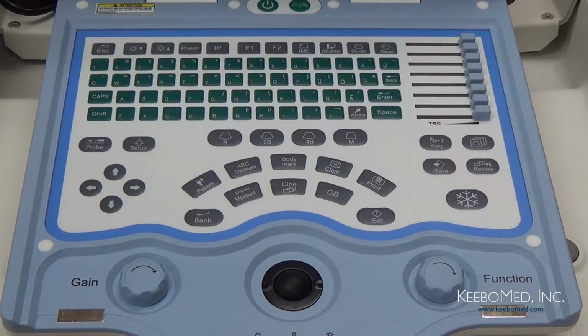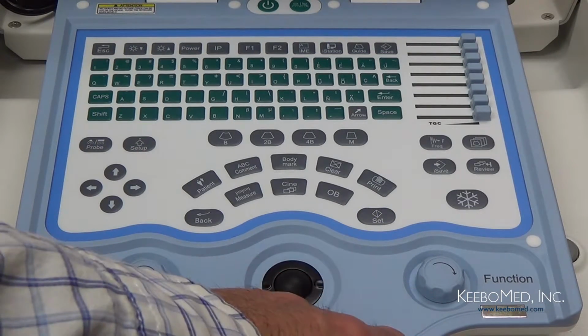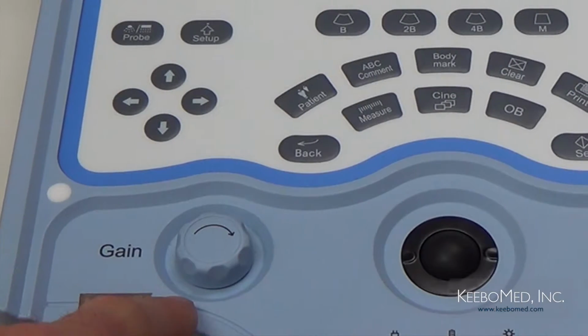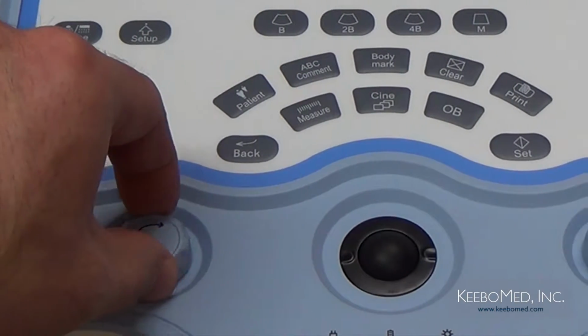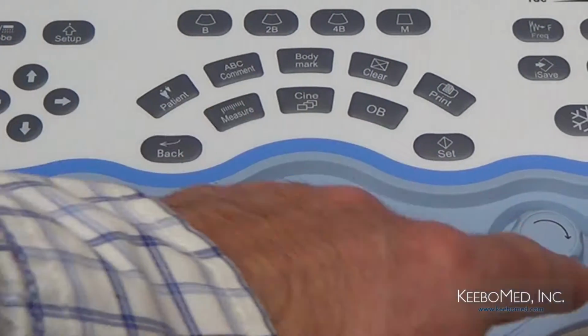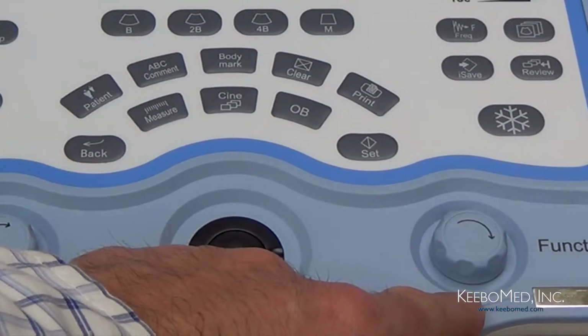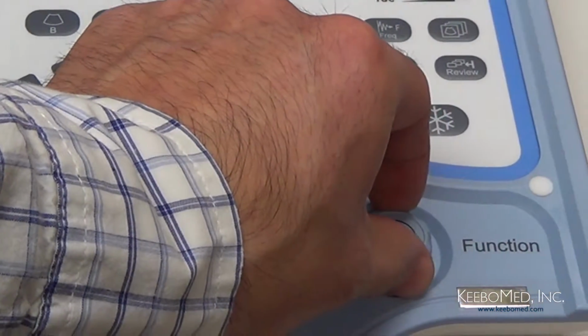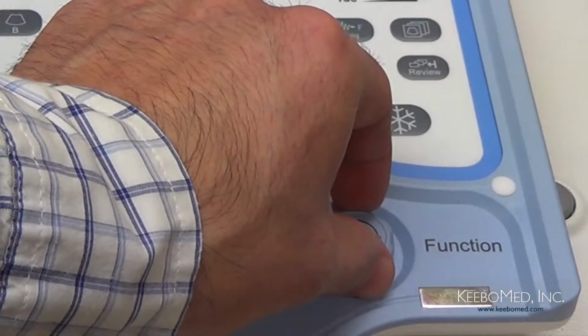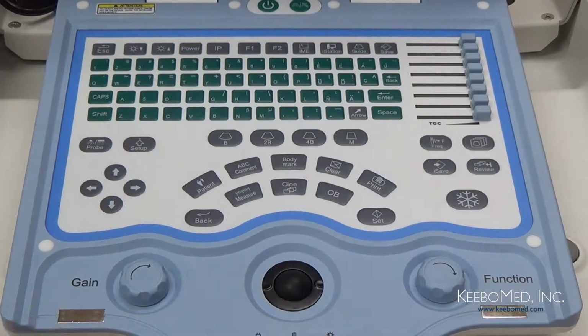There are two important knobs that are on each side of the trackball. Here on the left is the gain control, and by rotating it, the gain can be adjusted. On the right side we have the function control, which by rotating it will adjust the depth of the image. Now these knobs can also be used to rotate the direction of an arrow mark that is on an image.